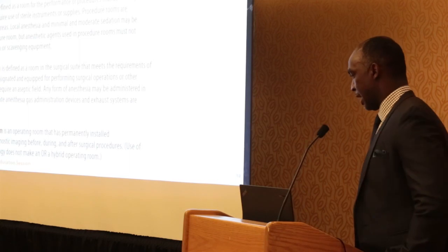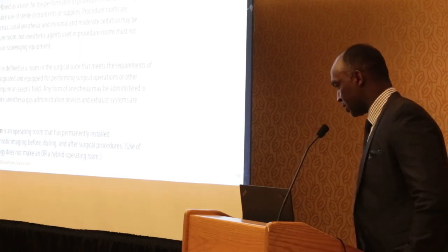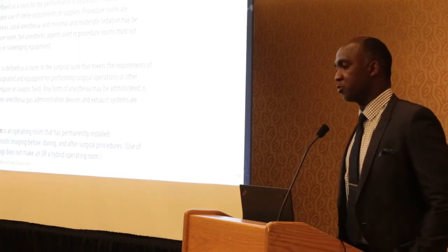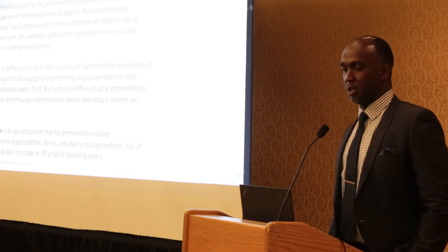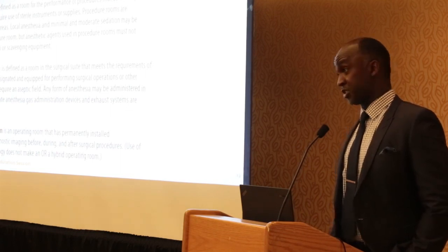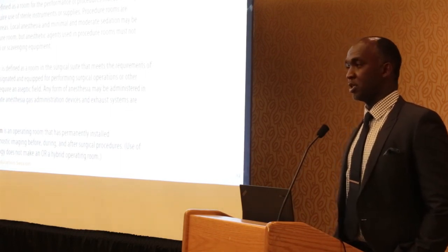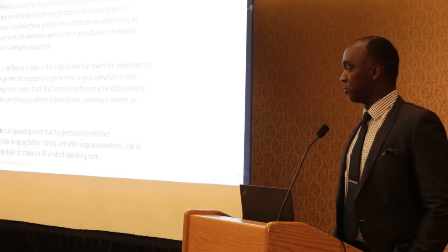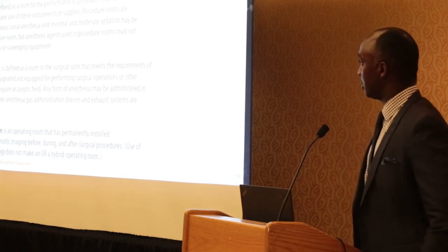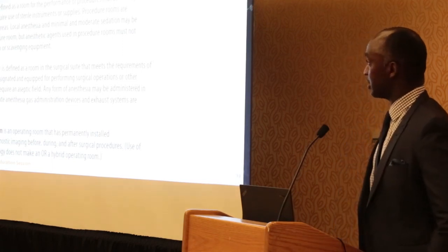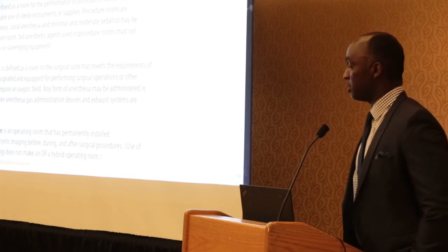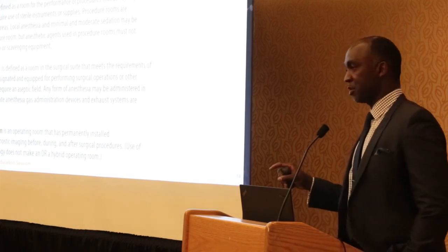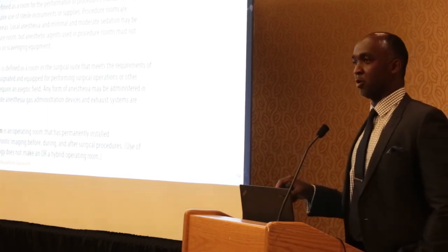I want to read this verbatim, because the operating room definition has changed in 2014. There's no longer Class A, Class B, and Class C operating rooms—that's from the old version. It's now defined as a procedure room, an operating room, and by extension hybrid ORs.